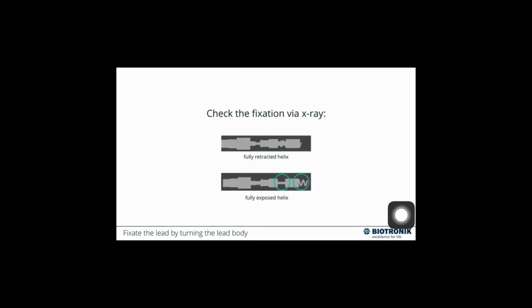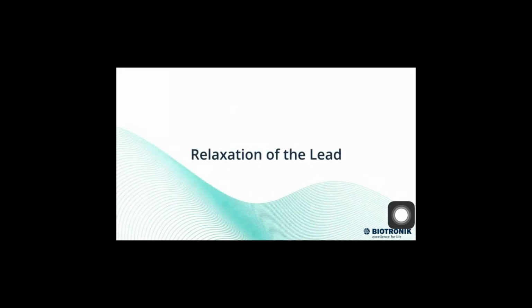Check the fixation via X-ray. The position of the helix can be clearly seen on the X-ray screen when the lead is X-rayed from a lateral view. If the helix is not completely exposed, try to extend it further by turning the stylet guide clockwise. However, if this does not succeed, remove the lead and start the fixation procedure again.